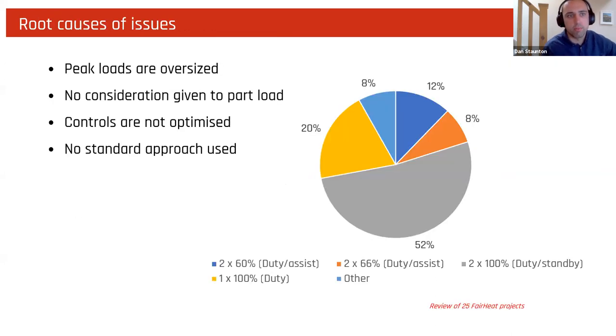There are a couple of root causes for this. We generally see peak loads still being oversized and the equipment being oversized because of that. Relatively limited consideration is given to part load, and controls are poorly optimized. There also isn't really a standard approach that's being coalesced around as an industry.